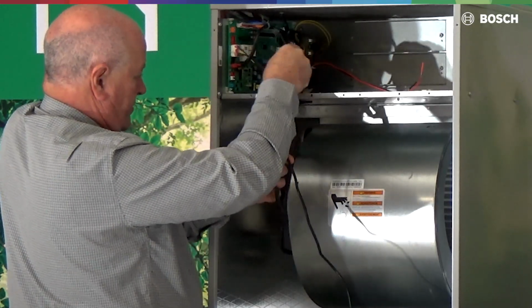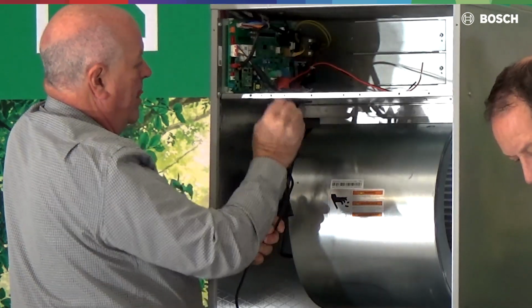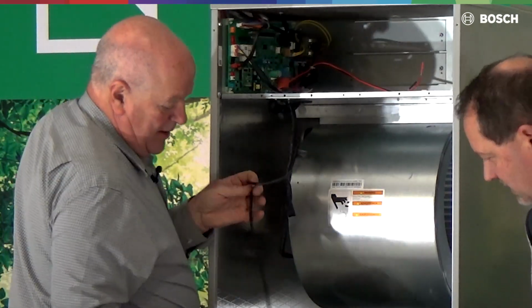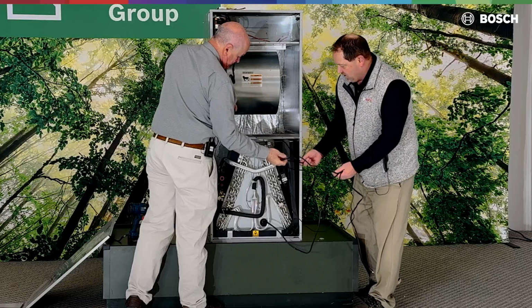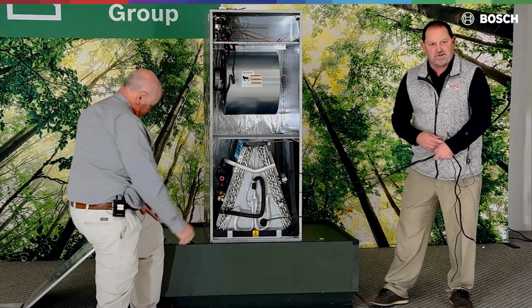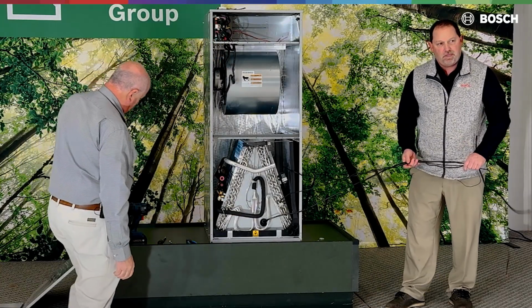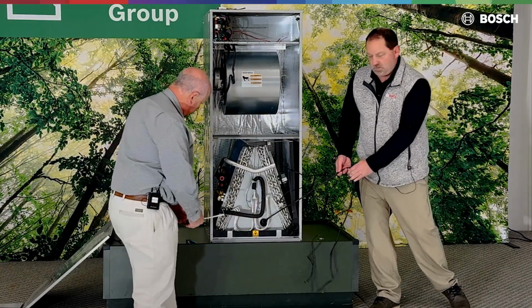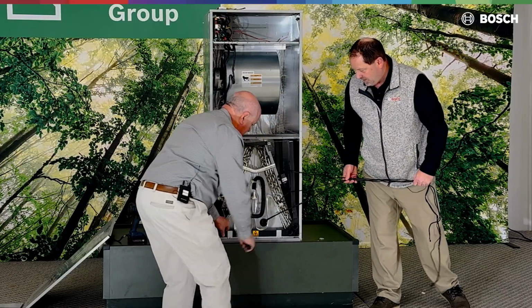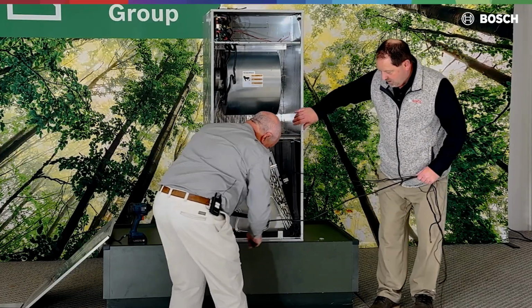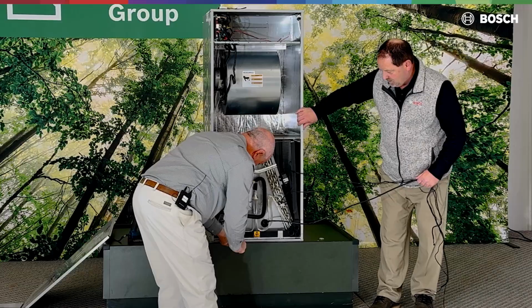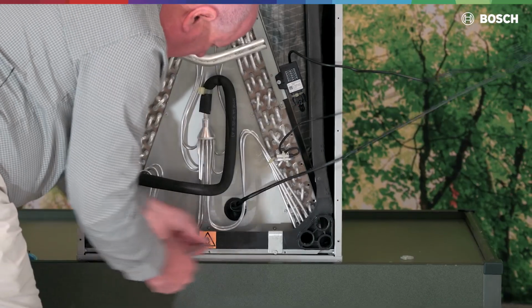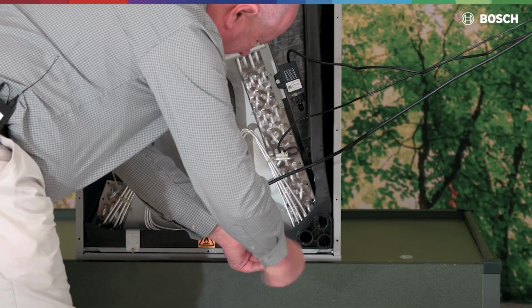Now that we have our sensors disconnected, we can remove our evaporator coil so that we can reposition our furnace and slide it back in. For us to do that, we have 2 screws down here on the pan. I think this actually comes out as a whole unit. Nope, it must come off there. We'll take these 2 off real quick. So the 2 brackets have to come off first. I believe so.